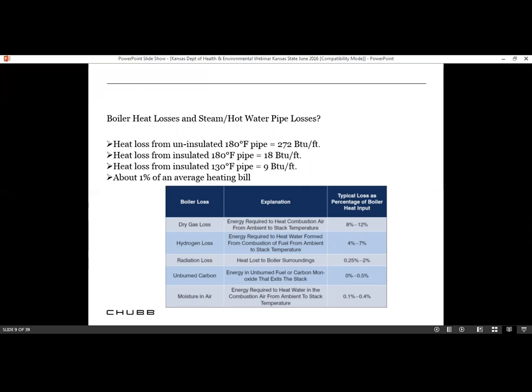Moisture in the air, energy required to heat water in the combustion air from ambient to stack temperatures. And if you look there, it's about 0.1 to 0.4%. So those two areas that I focus on a lot, because that could increase your overall cost.